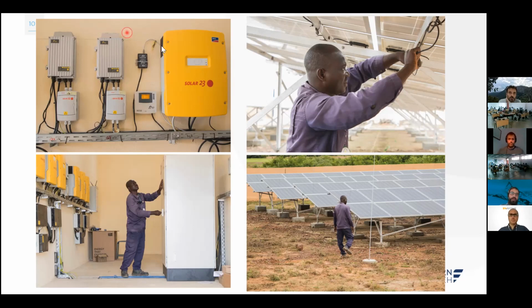This is the main interface with the devices, the way a user can go into the configuration of the devices and check the parameters. For example, with this one we will configure exactly the charging profile of the battery: the maximum current the battery should be charging at, the absorption voltage, floating voltage, and so on.